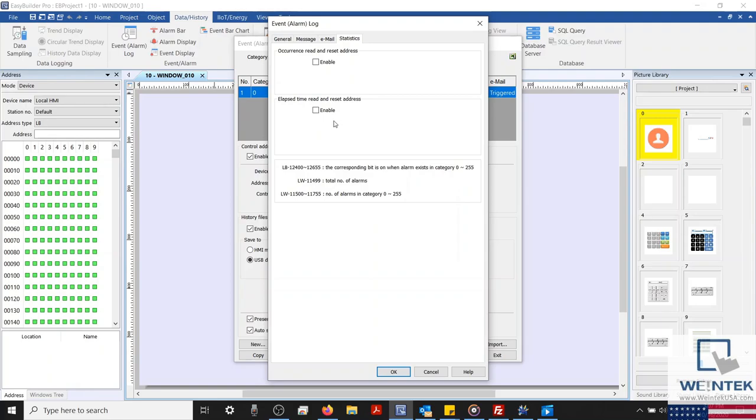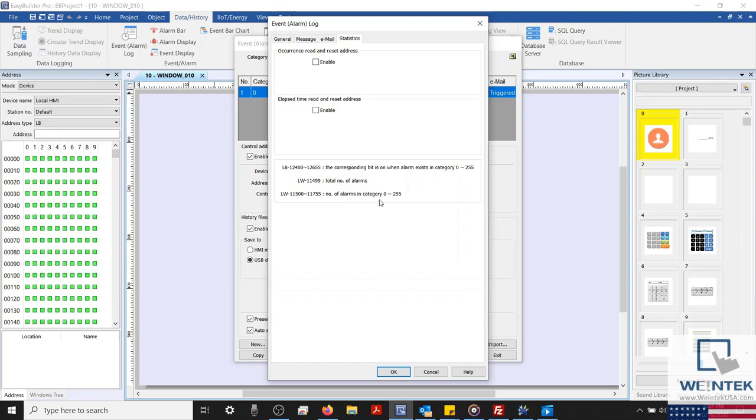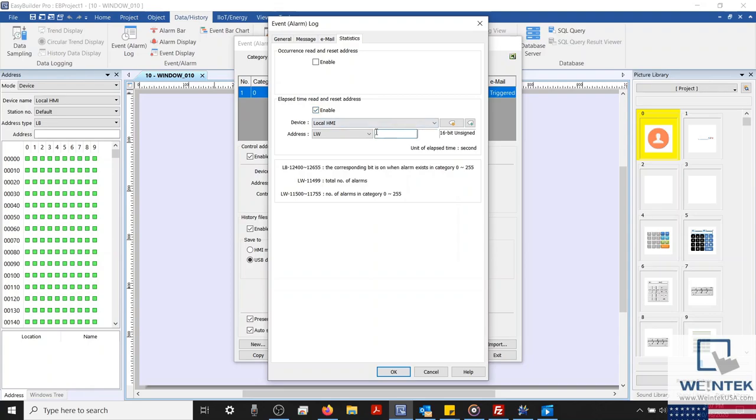Now below, we have some system registers that are built in. This includes a series of bits that can be used to detect when an alarm in a specific category is active. System register LW11499 will display the total number of alarms currently active. And a series of registers that will display how many alarms are active within a specific category. For now, let's configure our elapsed time address to LW3. And we'll also use LW11499 within our project as well.